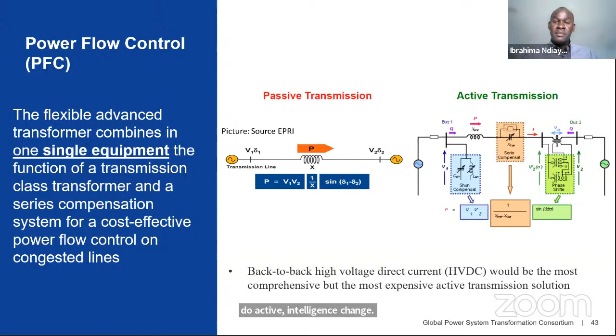The benefit of that is obviously cost and ease of integration into the actual network. Referring back to my first statement, transformers are what enable the grid, so we find them everywhere. Once we instrument a transformer, giving it the capability for active impedance change, we can hopefully more effectively control the power flow in the grid.